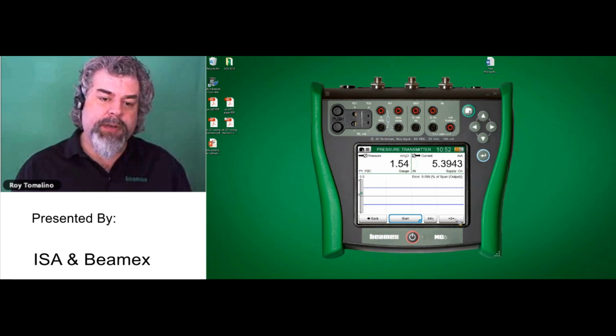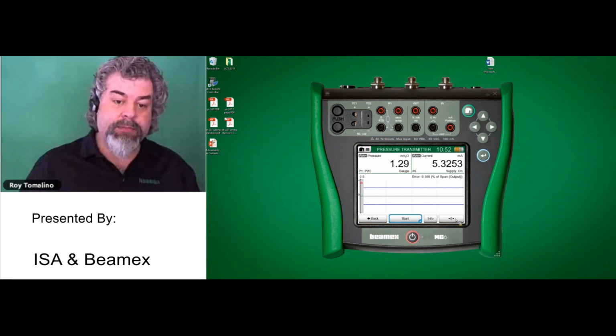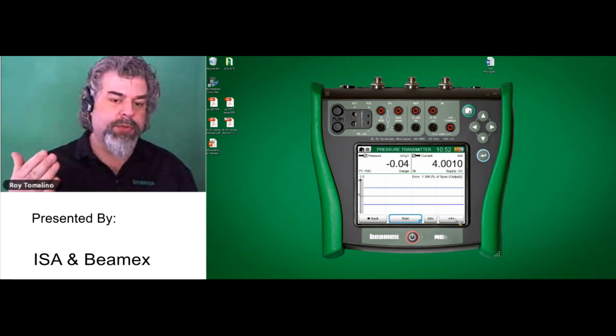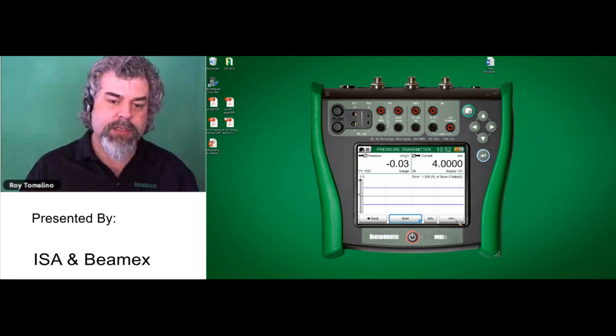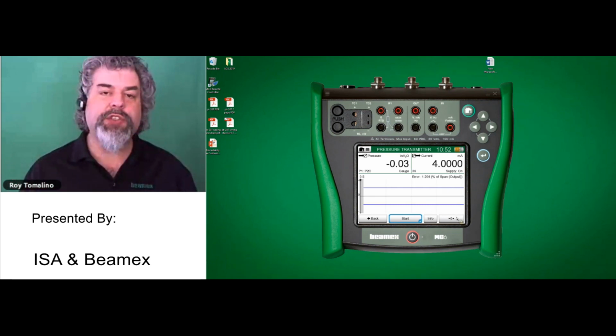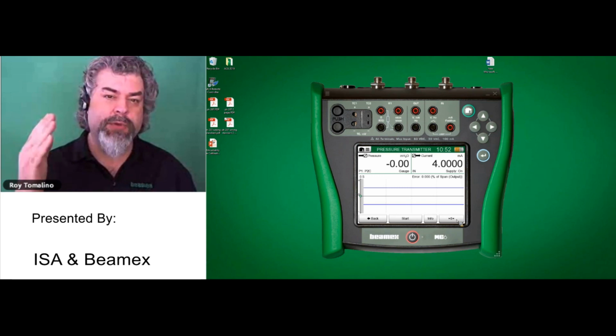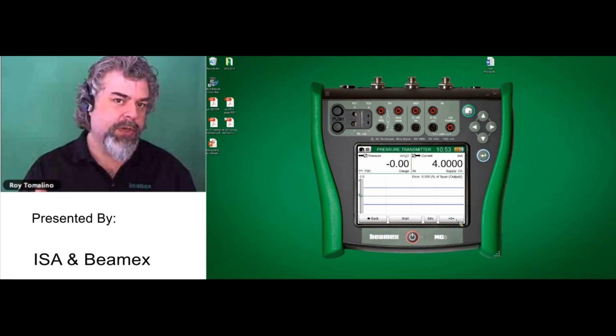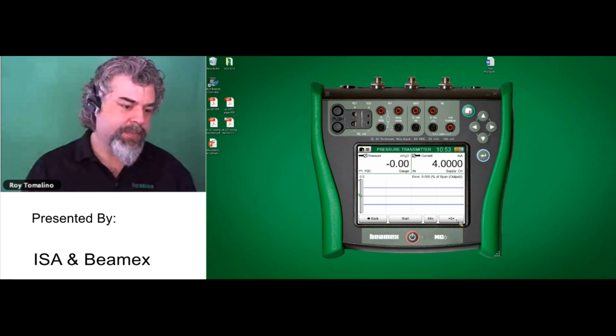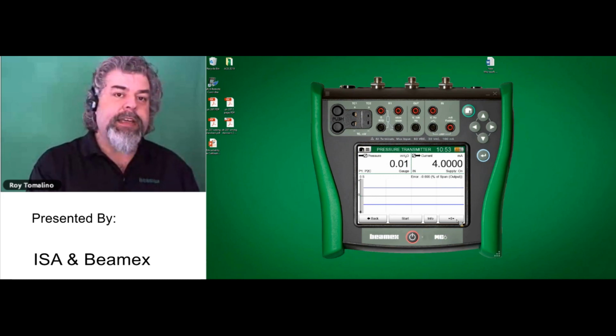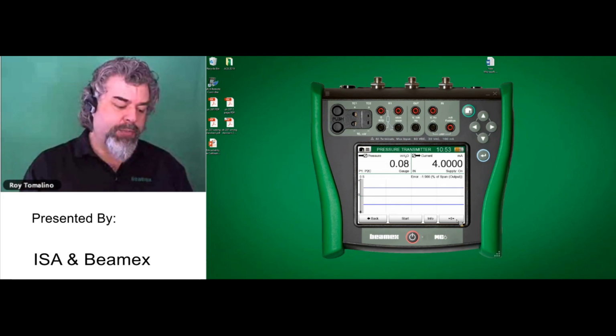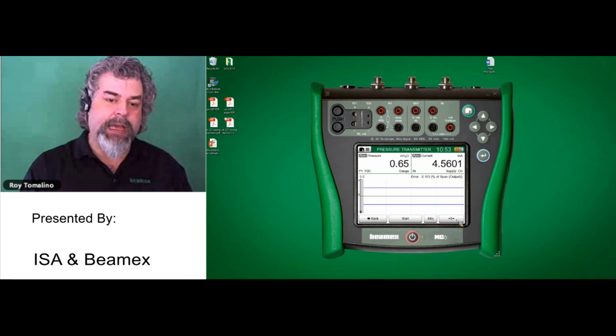Let me start up here, and let me vent out my pressure module. I always want to zero out my pressure module before I start the test, so this changes with barometric pressure every single day. Let me hit 0. I'm not zeroing the transmitter, I'm zeroing the transducer of my calibration standard. Okay, again, I don't want to measure 0 on a differential pressure, so I'm closing my vent, and now I'm increasing to about 1%.